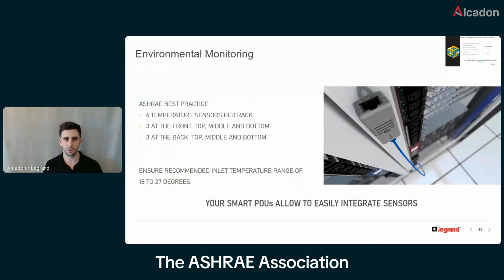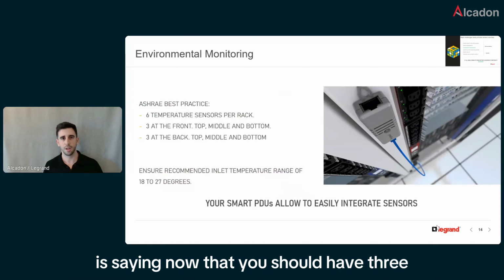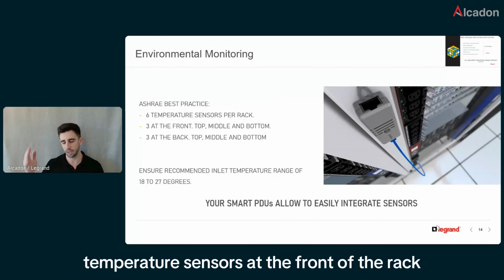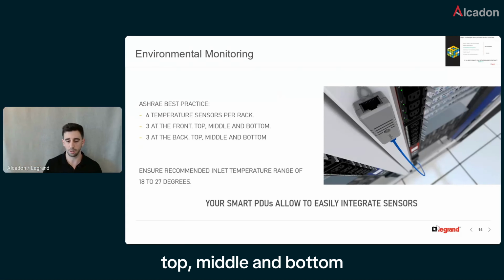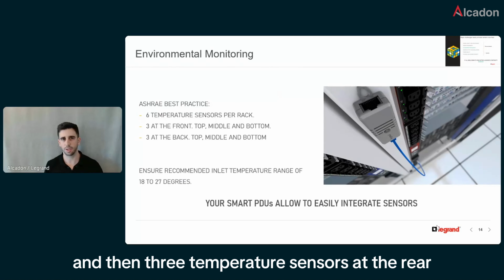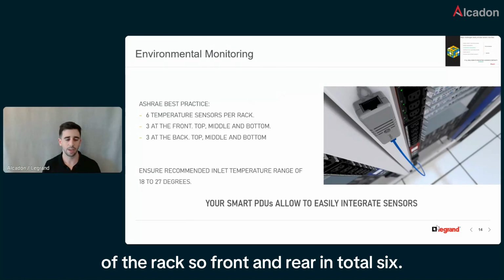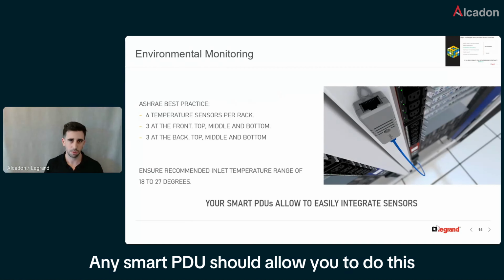The ASHRAE Association recommends having 3 temperature sensors at the front of the rack - top, middle, and bottom - and then 3 temperature sensors at the rear of the rack. So front and rear, 6 in total. Any Smart PDU should allow you to do this.